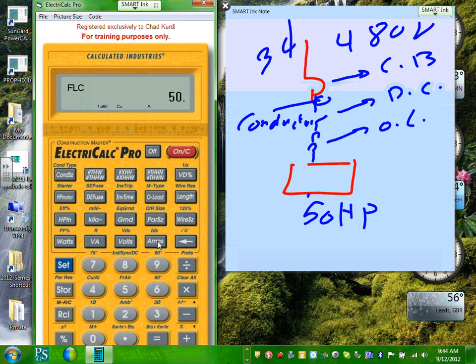Okay, now I need to size the conductor. Continuous load, so you have to hit the word set and hit wire size. Here's the conductor size, based on the 60-degree column. Now, since they're motors, you can size based on 70. So if you want to size on 70, just go change it to 70, 75. Okay, I need the circuit breaker. Hit the circuit breaker. Here's the size of the circuit breaker, 125.